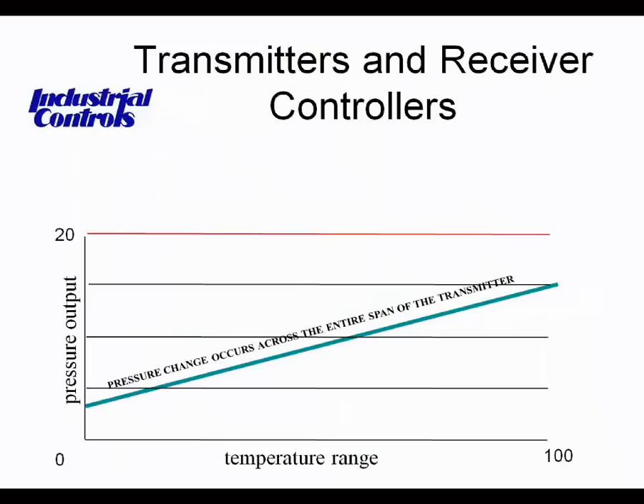What we also want to point out here is that you need to pick the right transmitter for the proper application. With a temperature range of 0 to 100, this specific transmitter would not be applicable for, for example, hot water, because the temperature of hot water would always be more than 100 degrees. So we wouldn't get that temperature-pressure relationship that we're looking for.